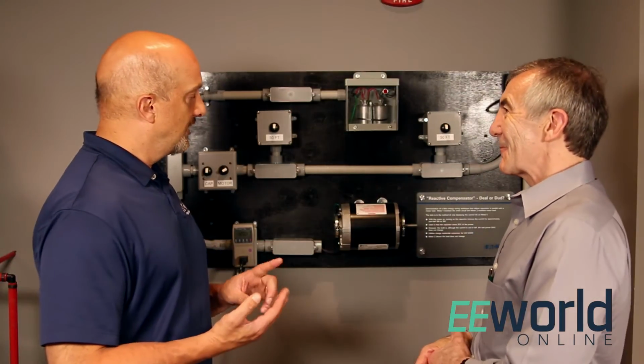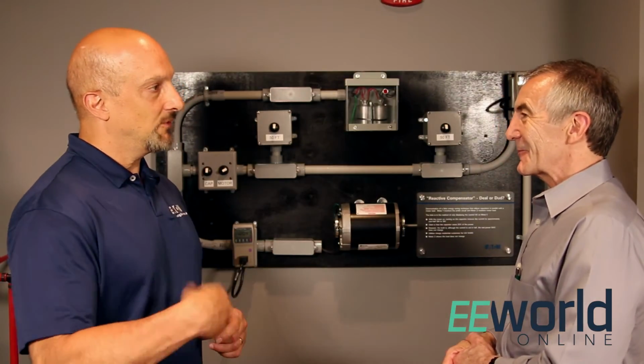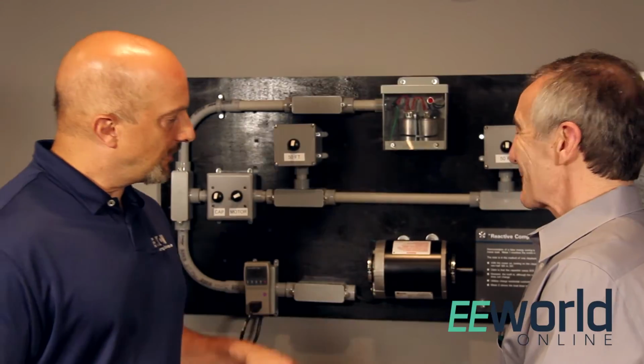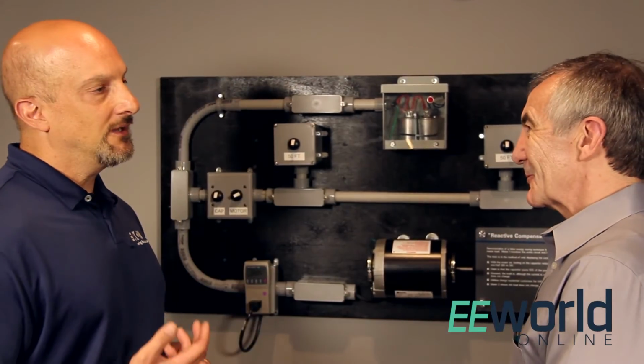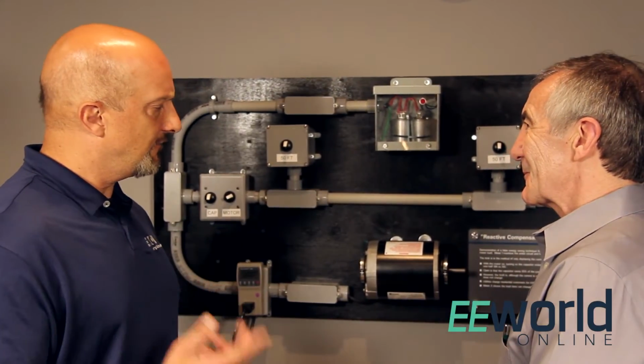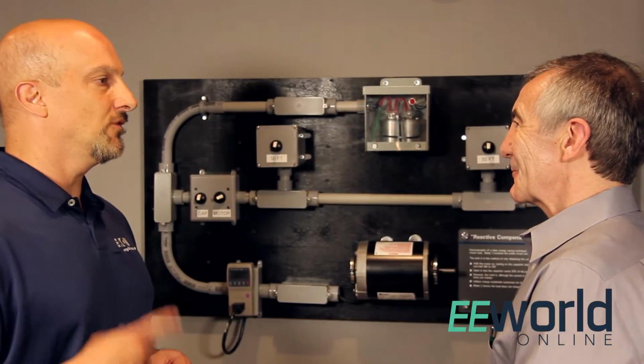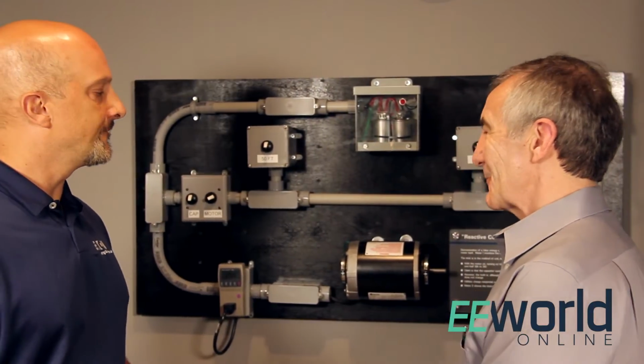What a motor needs to run is reactive power to make it spin, basically giving it the magnetic field, and it needs real kilowatts. But the only real kilowatts for a motor like this that's unloaded is basically the energy it takes to overcome friction, which isn't a whole lot.